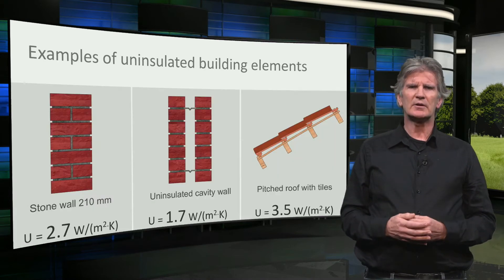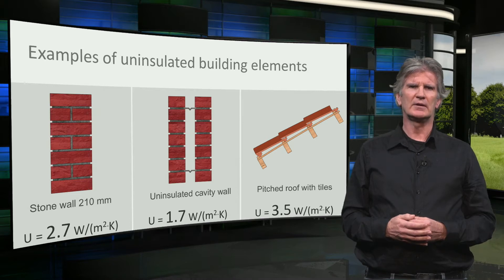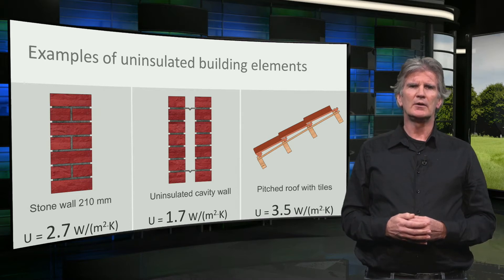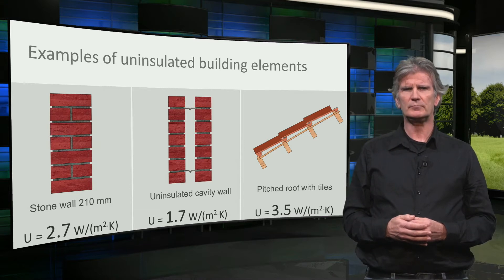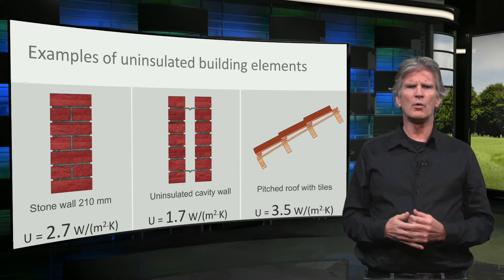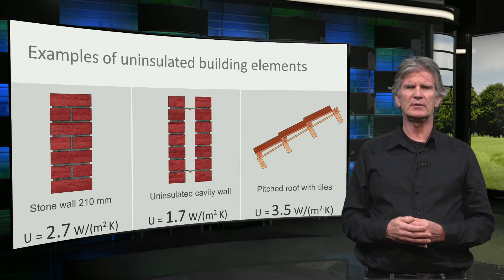Let's have a look at some examples of U-values for uninsulated building elements. An uninsulated masonry wall has a U-value of 2.7, a wall with an uninsulated air cavity 1.7, and a plywood roof 3.5.